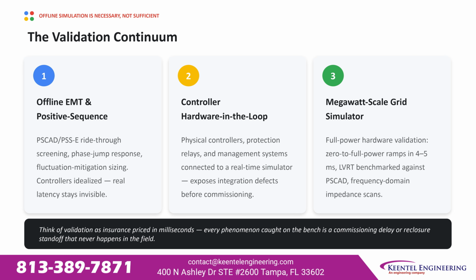Full power hardware validation, including 0 to full power ramps in 4 to 5 milliseconds, low voltage ride-through benchmarked against PSCAD, and frequency domain impedance scans. Think of validation as insurance priced in milliseconds. Every phenomenon caught on the bench is a commissioning delay or reclosure standoff that never happens in the field.